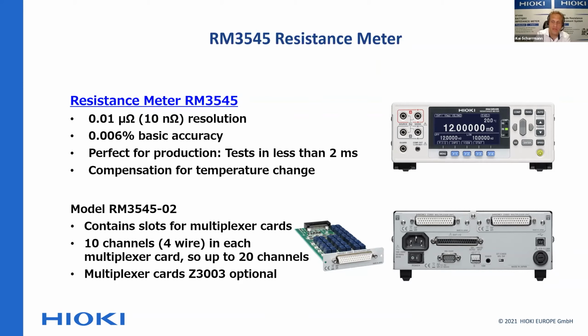But you really want to make sure, if you use this in production, that you already bought the unit that allows you to add these multiplexer units at a later stage, because that is a really, really fast and very, very good way of making a lot of tab weld measurements at the same time. You don't need 100 of these units just to do that, you just need one, and you have several multiplexer cards, 2 multiplexer cards, which means basically up to 20 channels at the same time.